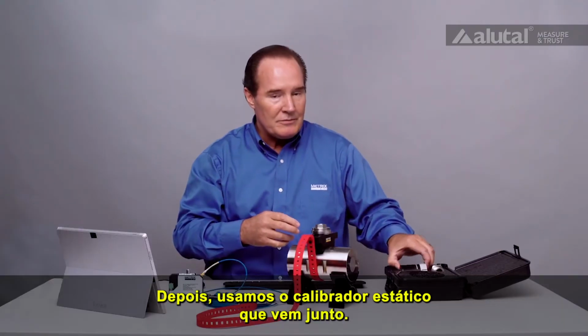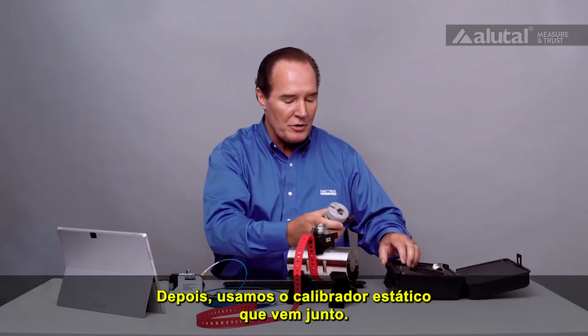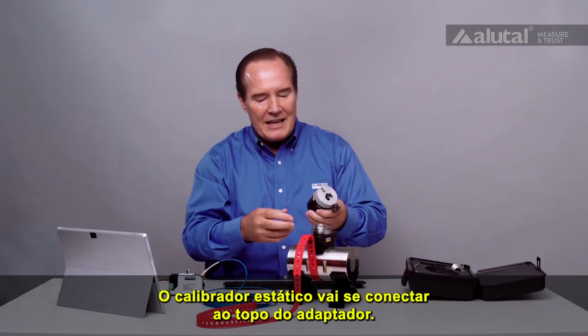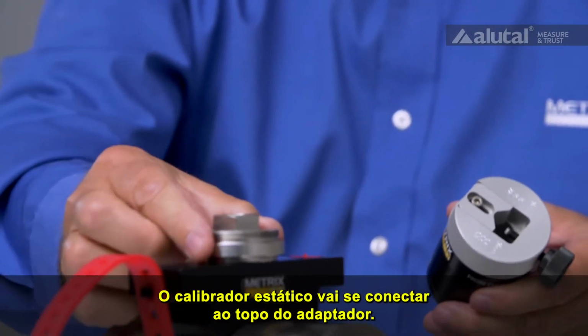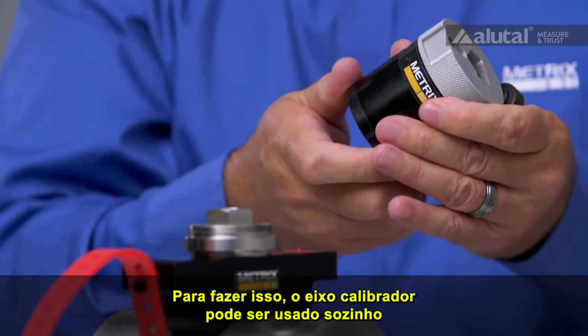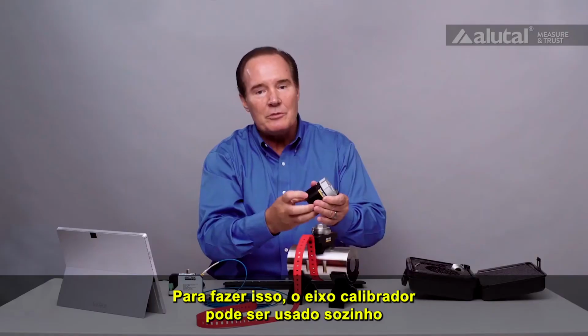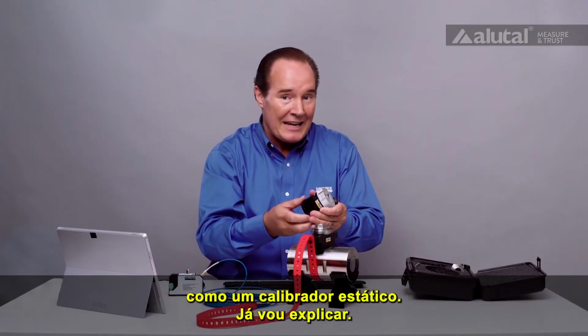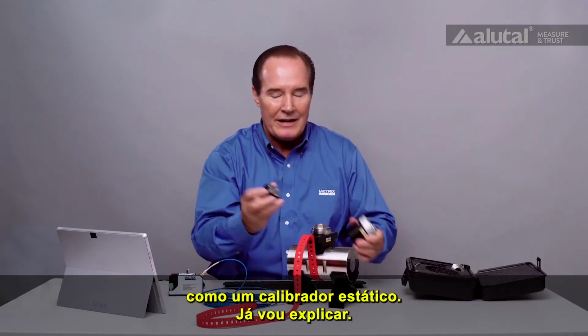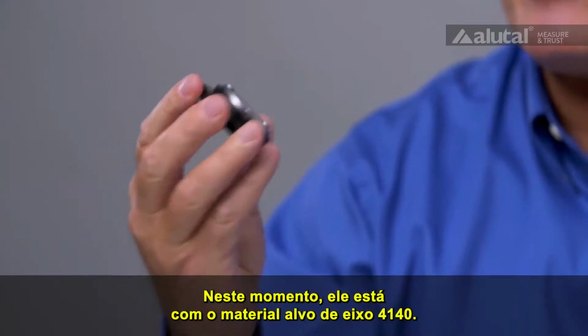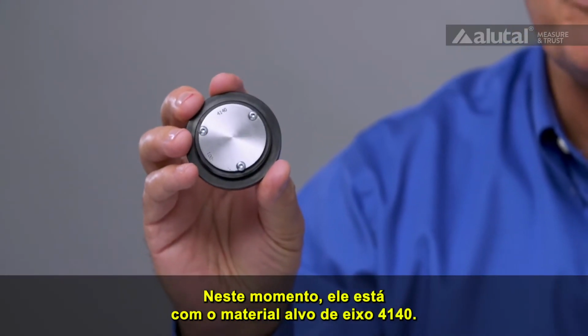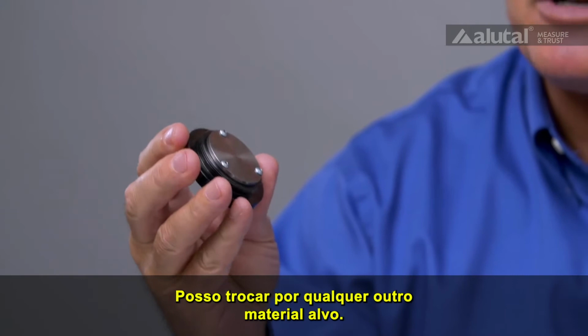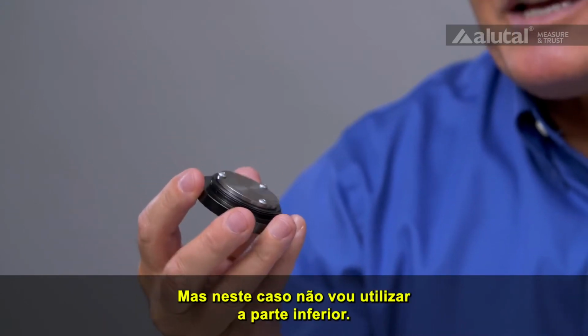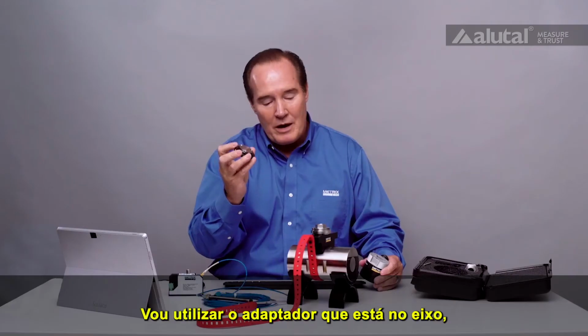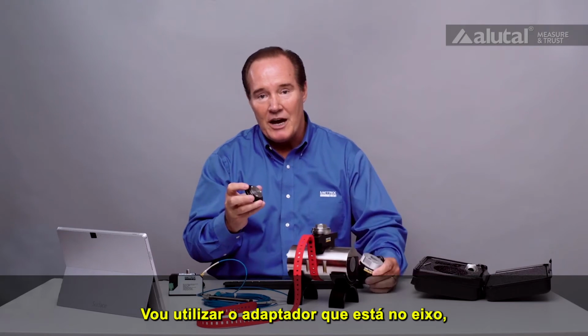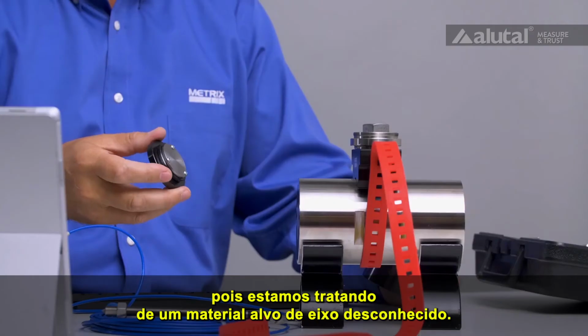Then we use the static calibrator that comes with it. And this static calibrator will go on top of this fixture here. The shaft calibrator can be used by itself as a static calibrator, and I'll show you what I mean by that. Right now it has a 4140 shaft target material on it. I can change that out to any target material. But in this case, I'm not going to use the bottom portion. I'm just going to use the adapter that's on the shaft because we're talking about an unknown shaft target material.